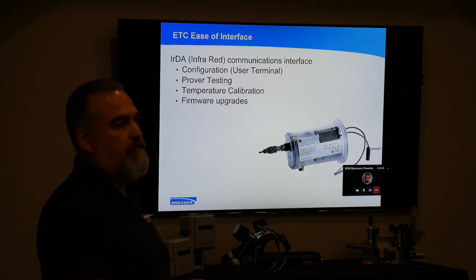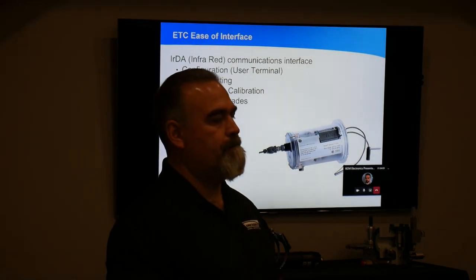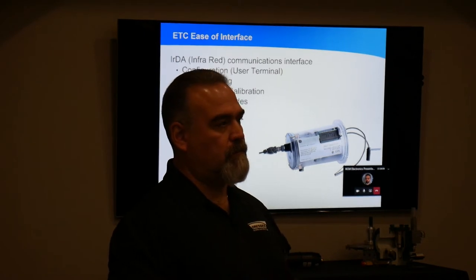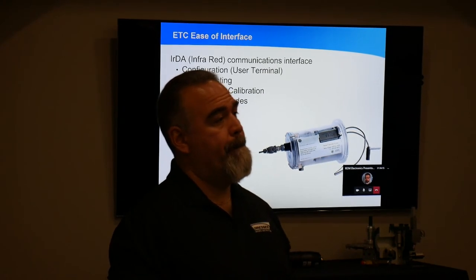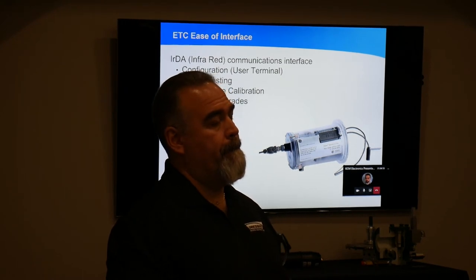Omar, I have a specific customer in mind regarding temperature calibration. Can you change that calibration to record an as-found, as-left value, or do you simply have the ability to move that calibration? Yes, based on your standard. Some customers are required to test any temperature probe upon install and then once a year. If they do an ice bath test and find they're off a degree, can they go in and change the calibration?